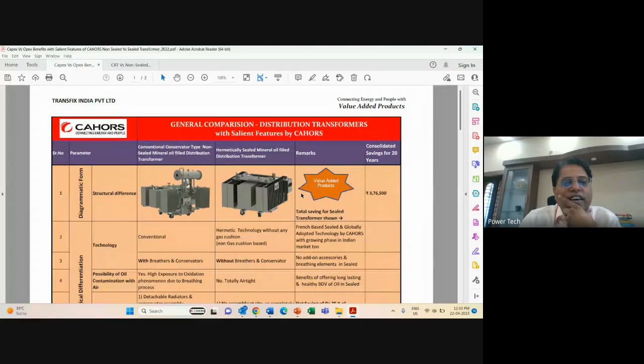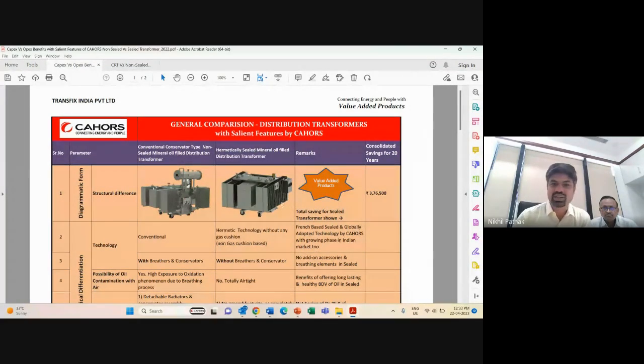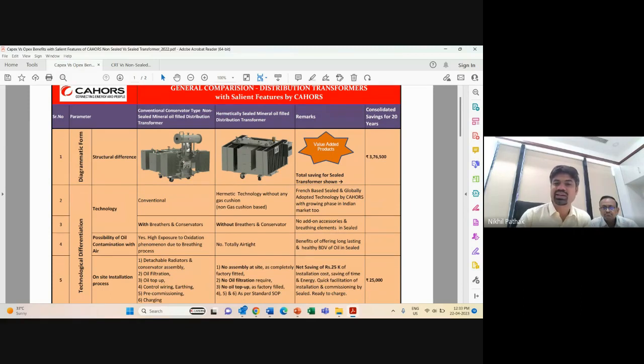Okay, great. So we are talking about the life cycle cost of the transformer. If we take an example of a 2 MVA transformer in the distribution segment, then without considering inflation and any non-standard incidental expenses, going by the books and standard operating processes of maintenance and care done by any customer for any normal conventional transformer, in a span of 20 years any customer directly or indirectly spends around 3.5 to 4 lakh rupees. So if we adopt the sealed type of transformer, effectively this amount can be saved.